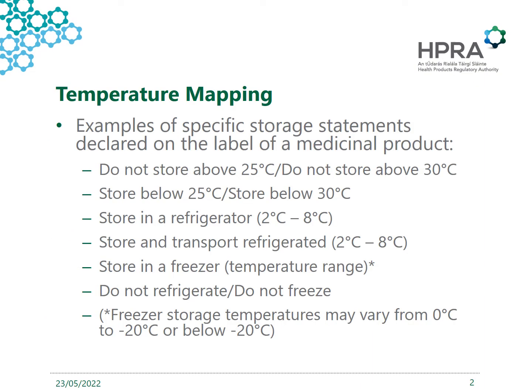Most medicinal products have specified storage conditions with respect to temperature. Temperature mapping is important for verifying the efficacy of the storage areas, systems and equipment within, to maintain the required conditions and ensure the safety, efficacy and quality of the medicinal product. It's also a requirement outlined in Chapter 3 of the EU GDP guidelines.